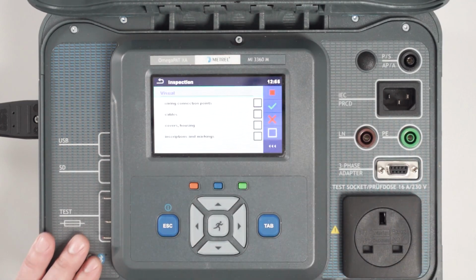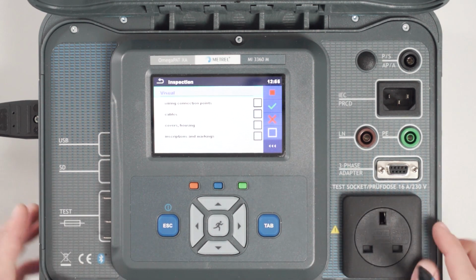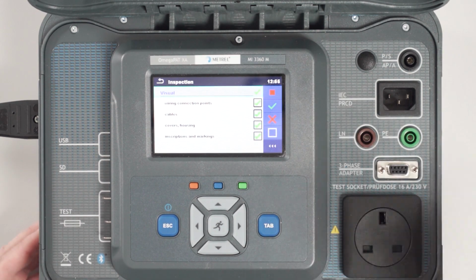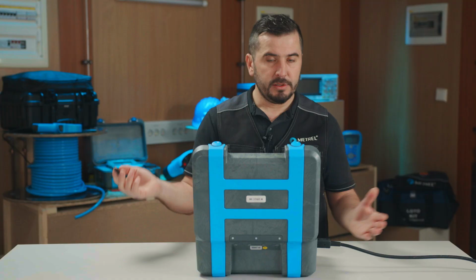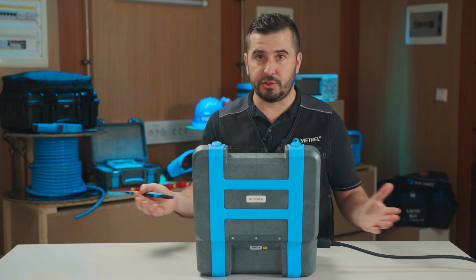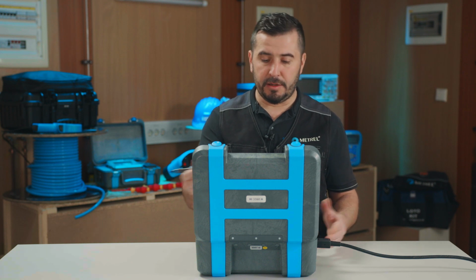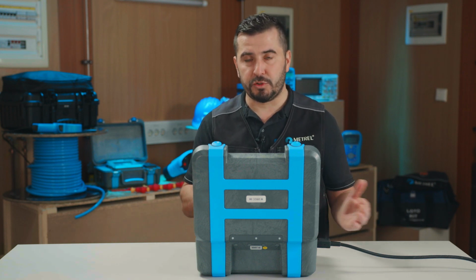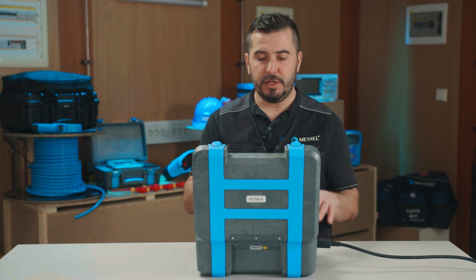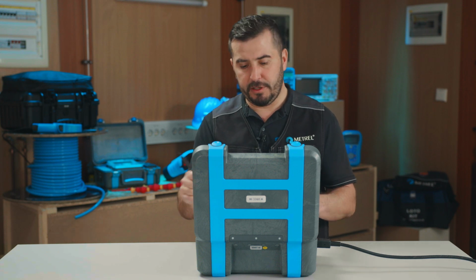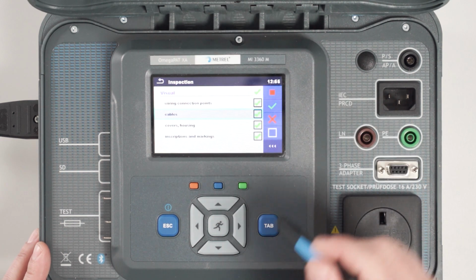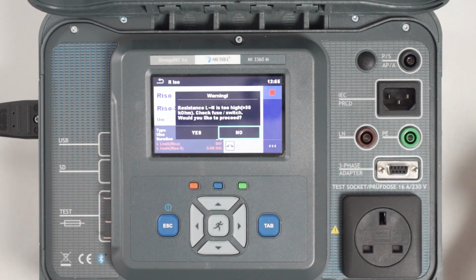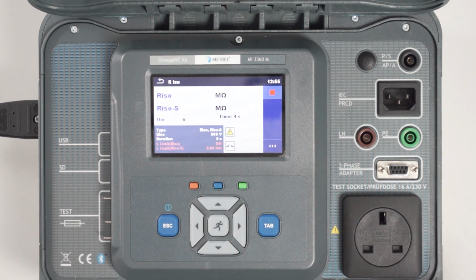So we press start. First is our visual inspection. We confirm it here. We can also say that some of the parts of this visual examination failed, though this will not allow us to proceed with the test, as the tester is set to end if fail. So we will select here that everything passed. We finish this first step. Now this pop-up warning, which was also explained in some other videos, we confirm it. And now we start with the insulation resistance test.